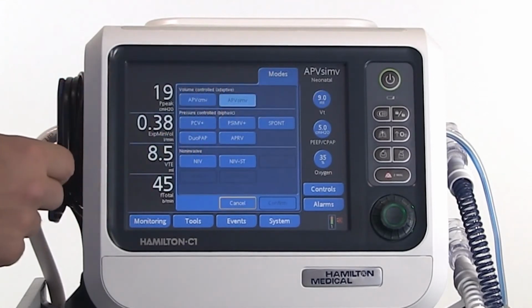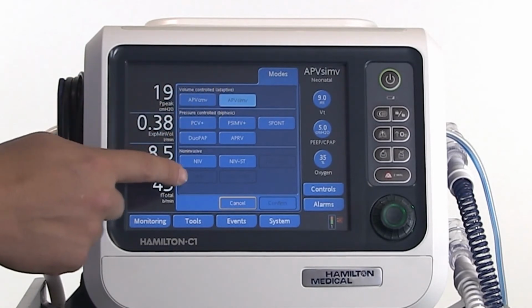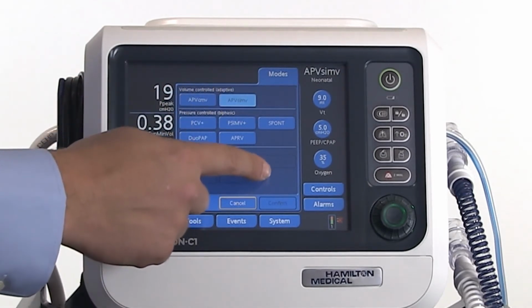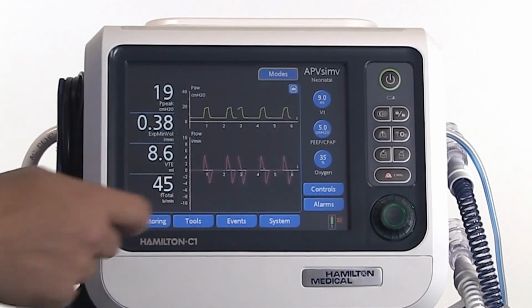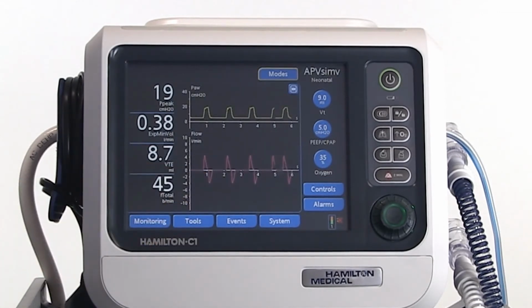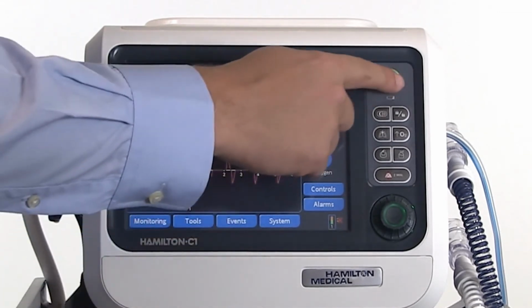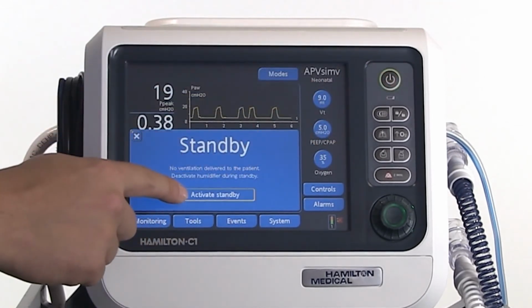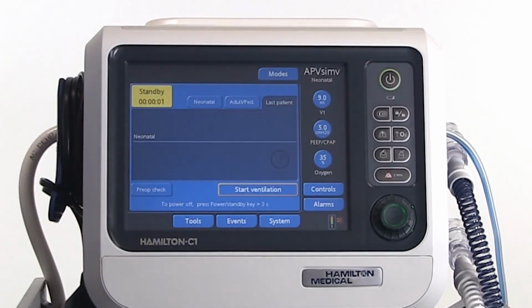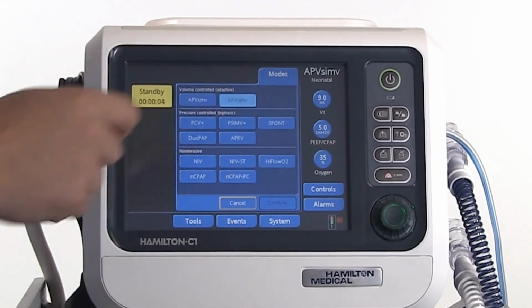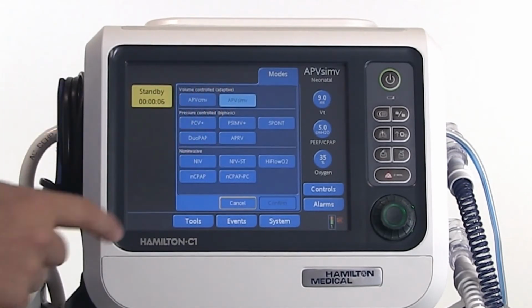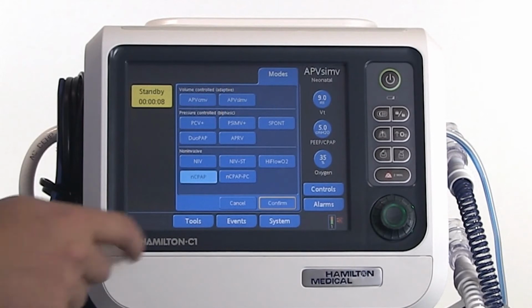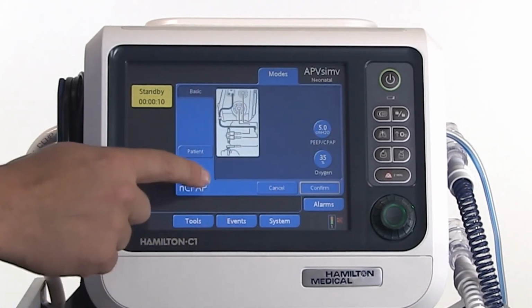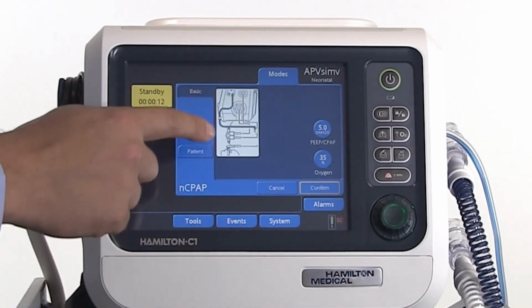Please note that while ventilation is running, you can switch to any other mode except to NCPAP or NCPAP-PC, or high-flow oxygen therapy. To switch to the NCPAP modes, you need to go back into standby, open the modes window again, and select the desired NCPAP mode. Make the necessary changes to the system according to the instructions on the screen.